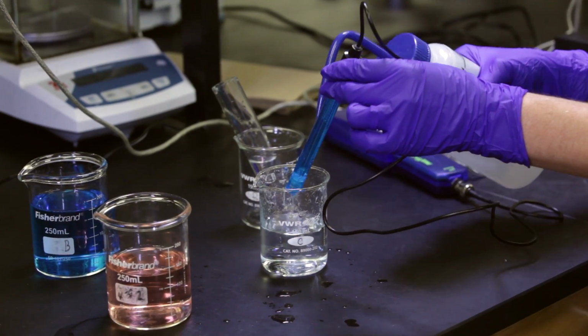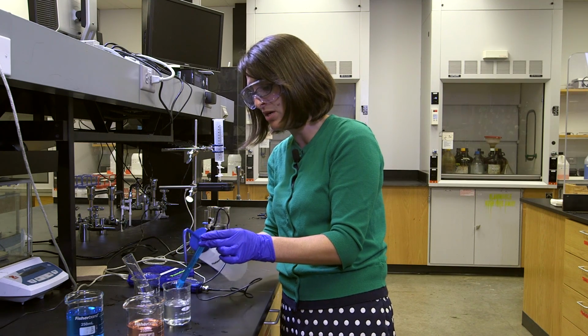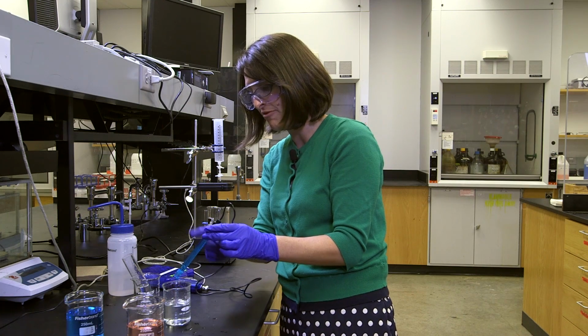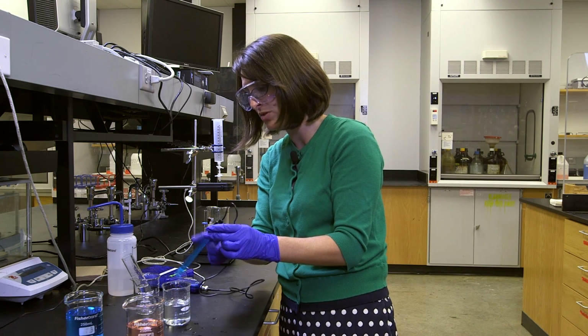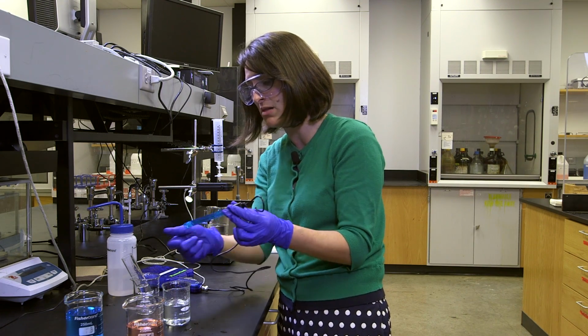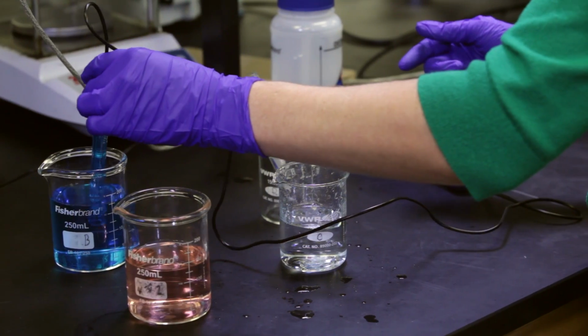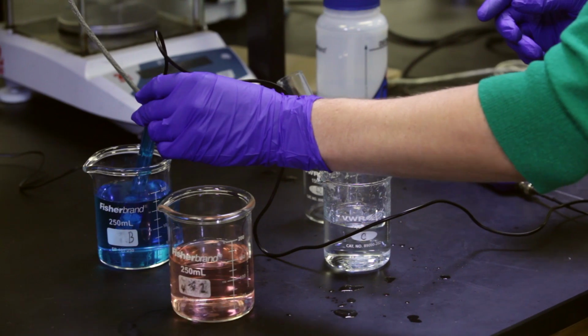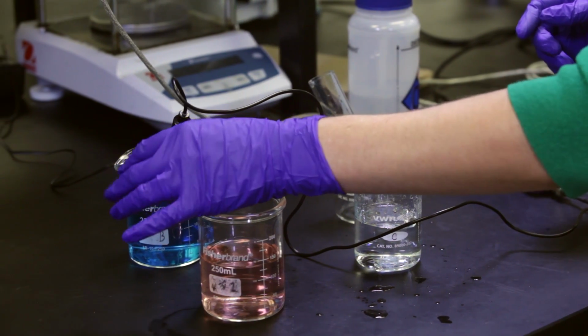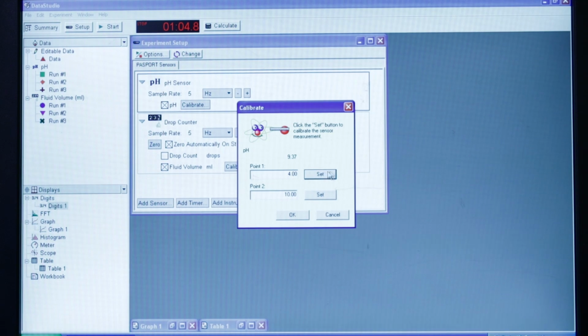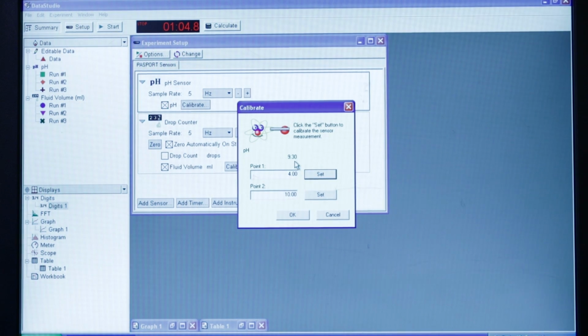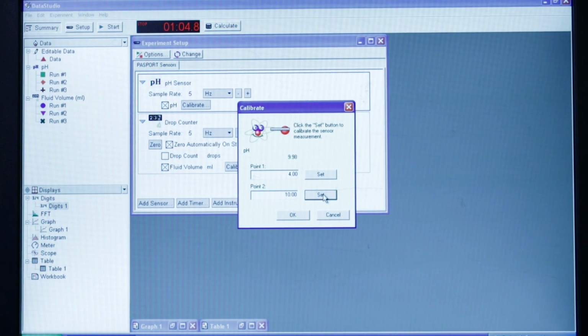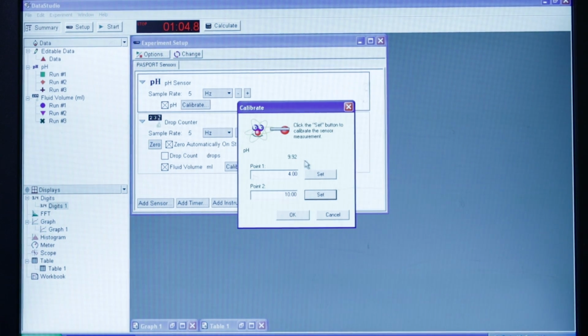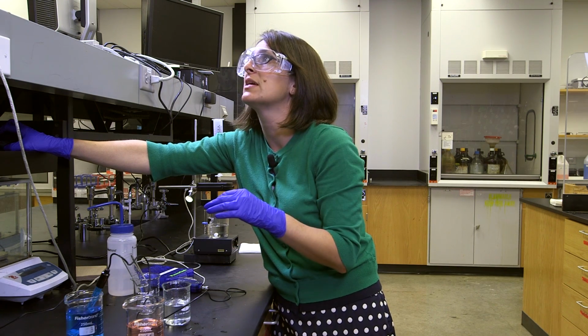If I took it straight from my pH 4 buffer into my pH 10 buffer, then my reading's going to be off because I'm changing the pH of the solution. So I'm going to rinse it off, and then tap a little bit off that glass bulb without actually touching the glass bulb. And then I'm going to gently set it in my pH 10. So the blue is my pH 10 buffer. Right now it's reading about 9.3, which is pretty close, but we're going to set it to 10. And there it is, about 9.9. Okay, so we can stir it around and you can reset it again.